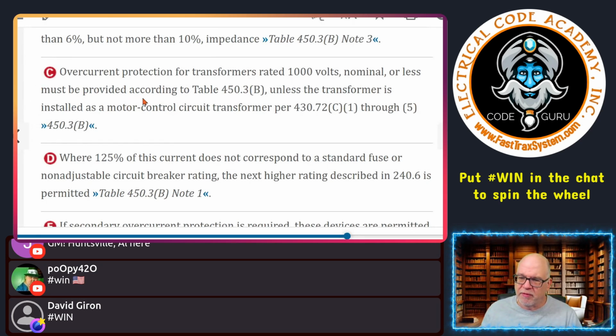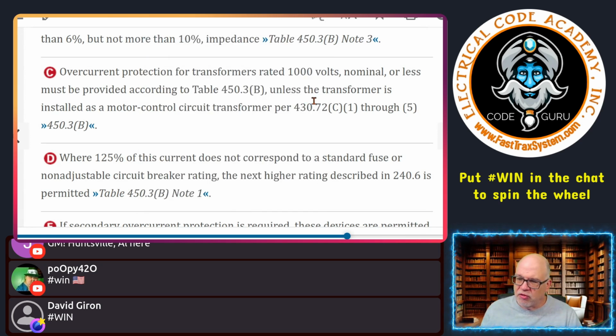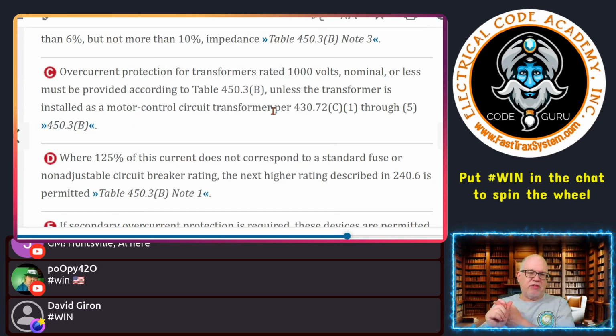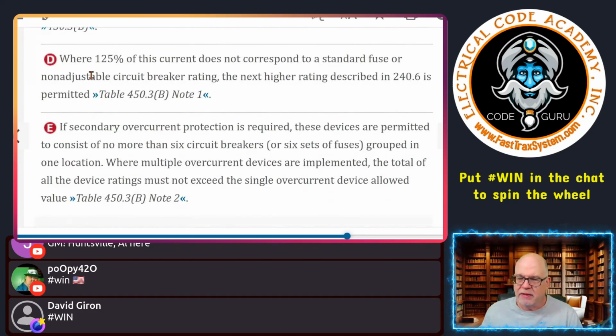Overcurrent protection must be provided in accordance with Table 450.3(B), unless the transformer is installed as a motor control circuit transformer per 430.72(C)(1) through (C)(5), and again, that's there. So that is unique for that application. If the transformer is a motor control circuit transformer, there are unique allowances that you would follow. We're not going to get into that.